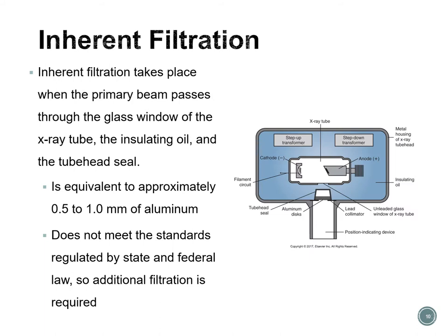Inherent filtration takes place when the primary beam passes through the glass window of the x-ray tube, goes through the insulating oil, and through the tube head seal. The inherent filtration of the dental x-ray machine is equivalent to approximately 0.5 to 1 mm of aluminum. Inherent filtration alone does not meet the standards regulated by state and federal law, and therefore added filtration is required. The glass window, oil, and tube head seal together constitute inherent filtration.